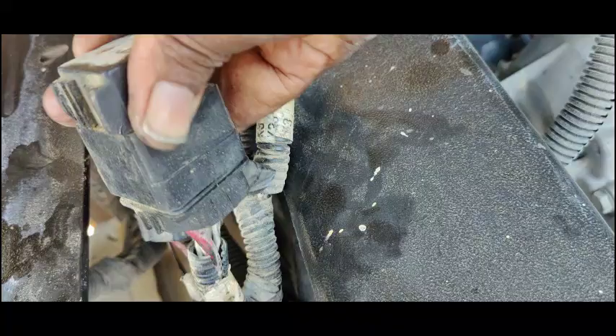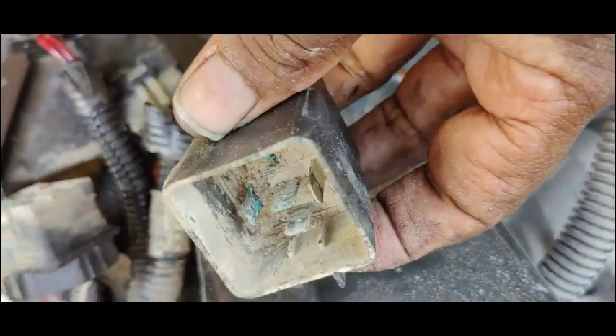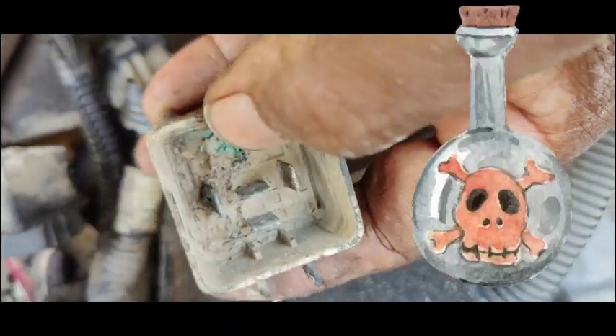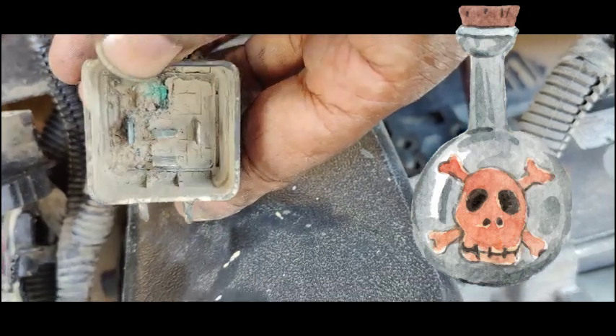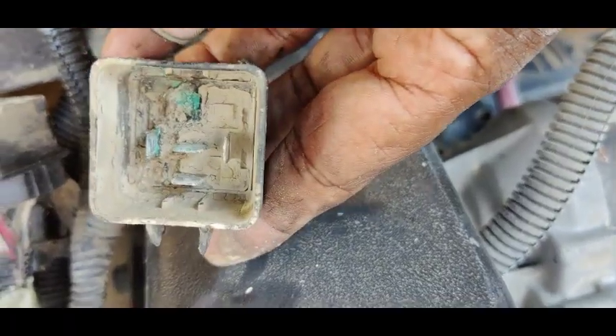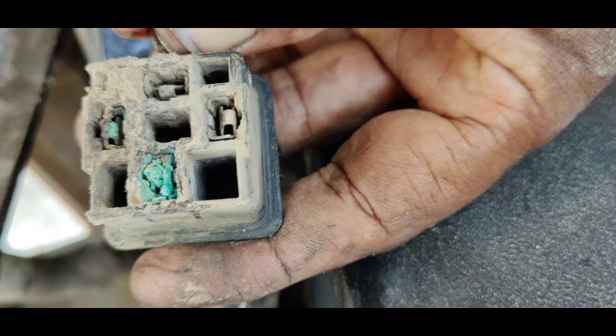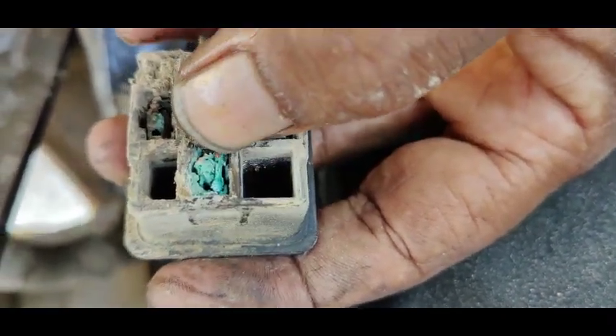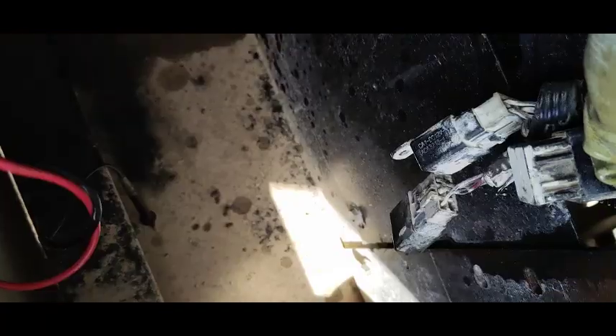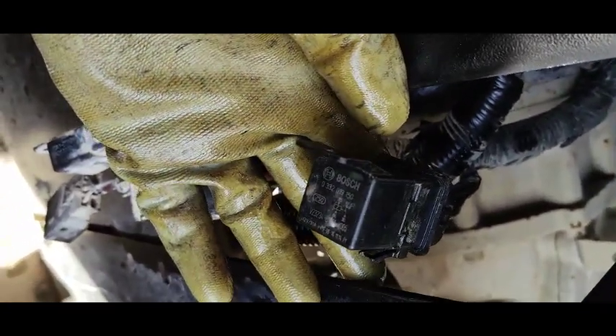This one is my preheat relay. I'm going to check this one too. You can see my first relay was very dirty. This leg is broken — you can see the condition of this relay is very bad. I'm going to replace this preheat relay. I'll change this relay, then fix both relays back and try to start the engine. I've fixed back the start relay and changed the preheat relay.